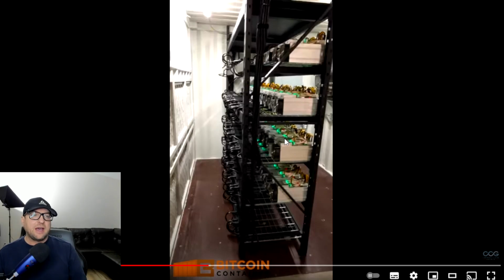So what we did is we had regular 30 amp PDUs with 4 plugs that ran directly into these. I think the L3s could accommodate one per each plug, so we could run 4 L3s per PDU. But the S9s we were running could only run 3 of them on there because it only had 30 amps, so you didn't want to burst your PDU or breaker every time you turn those on. Just keep that in mind when you're building something like that.